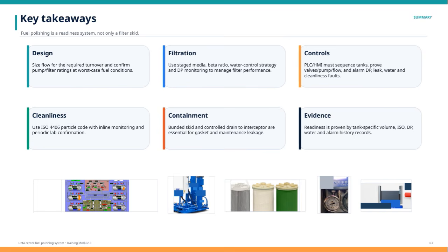Cleanliness monitoring is essential, so use the ISO 4406 particle code along with inline monitoring systems and periodic lab testing to confirm fuel condition. For containment, having a bund skid with controlled drainage to an interceptor is necessary to manage any gasket or maintenance-related leaks. Lastly, evidence of readiness comes from maintaining detailed records, including tank-specific volume measurements, ISO cleanliness codes, differential pressure data, water detection, and alarm history. These elements together ensure the fuel polishing system keeps the fuel in optimal condition and ready for use at all times.